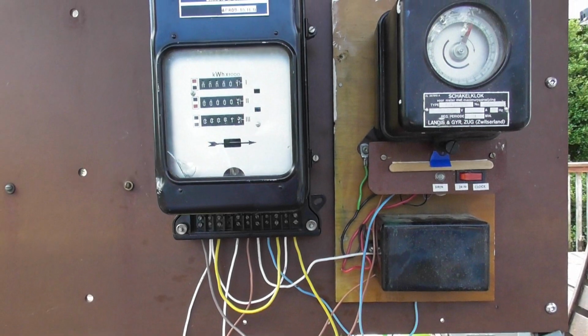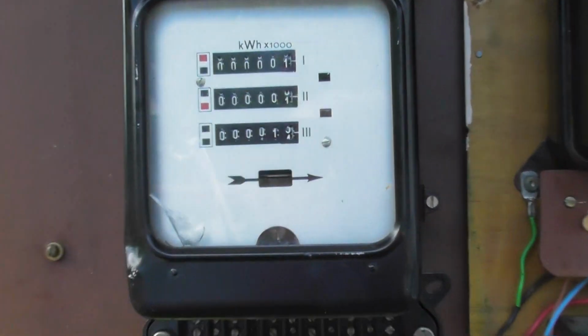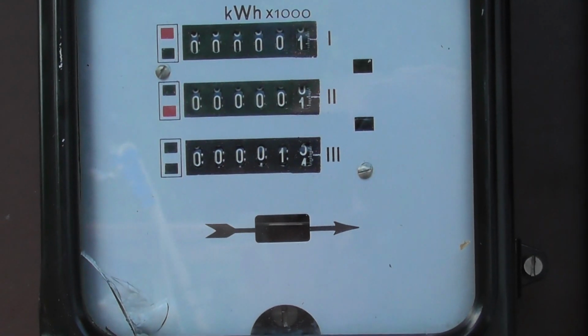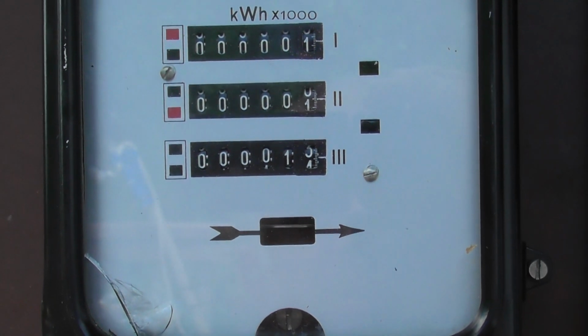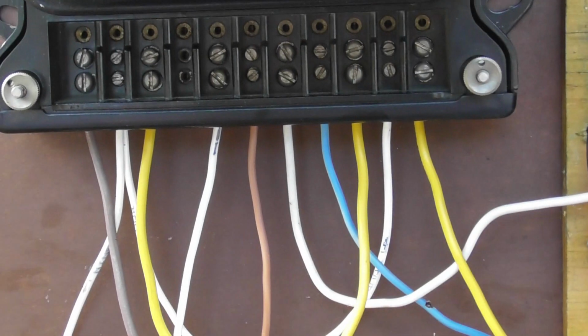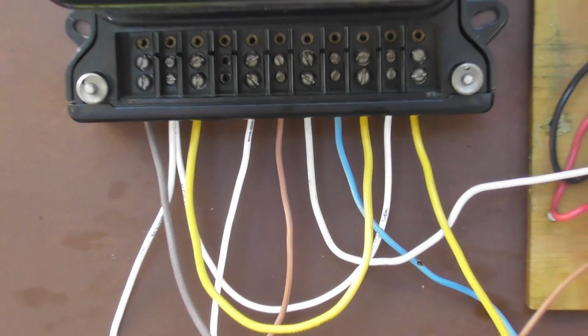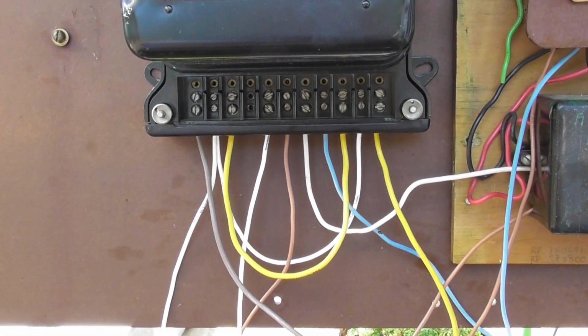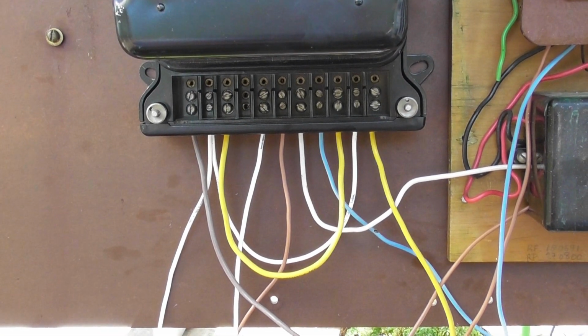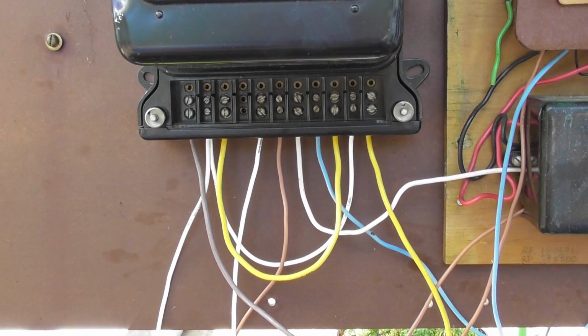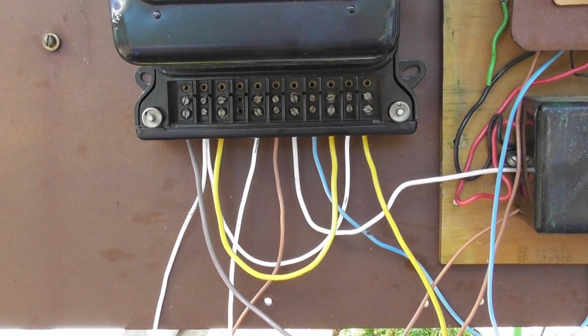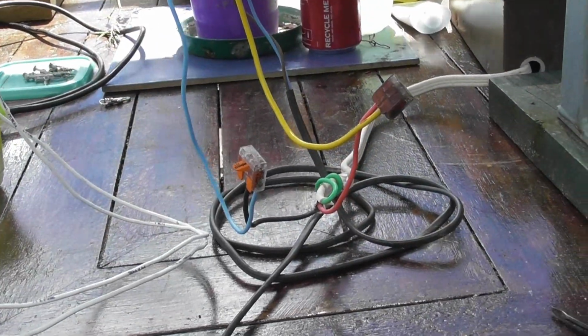I've wired up the meter a little bit different today. I thought I'd get some more speed. Got a 2 kilowatt load on it. You can see the disc is flying quite a lot faster now. The potential coils on the meter are at 110 volts, but the main supply is at 230, 240 volts. Going in from the brown wire on terminal 1, yellow out in 3, in on 10 and out to a couple of connectors here, which goes to a 2 kilowatt heater here.